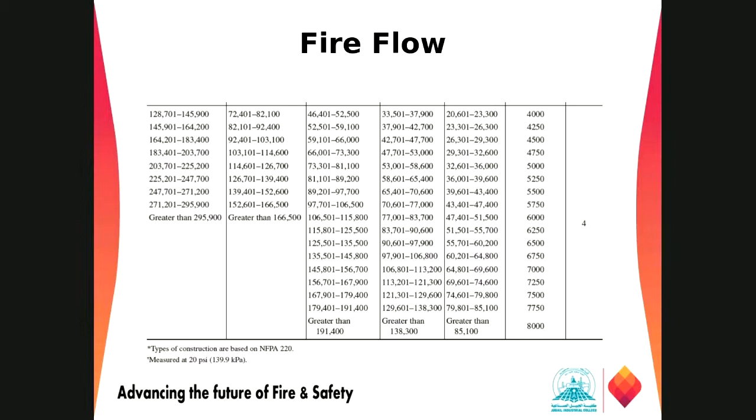So while you are reviewing a plan and looking for those things, we have to follow the IFC for the various equipment and various connections. We have to look at the IFC code for the flow requirement from the hydrant and what the duration will be. Based on that, we have to size our underground fire water networks for those localities.